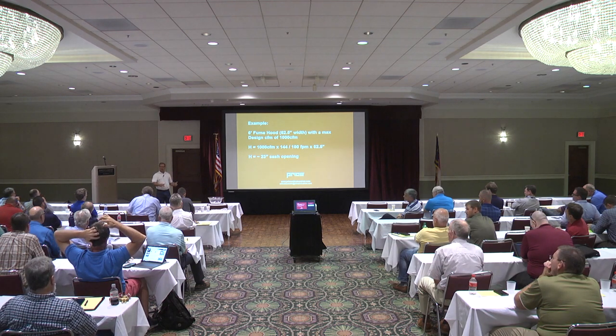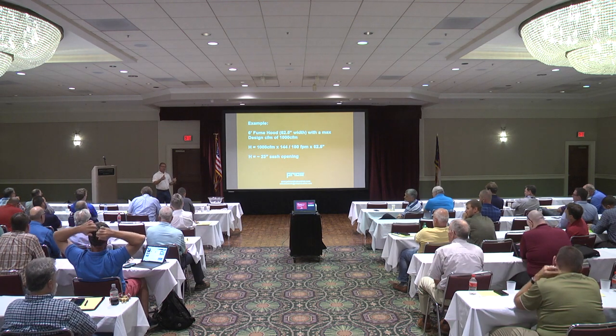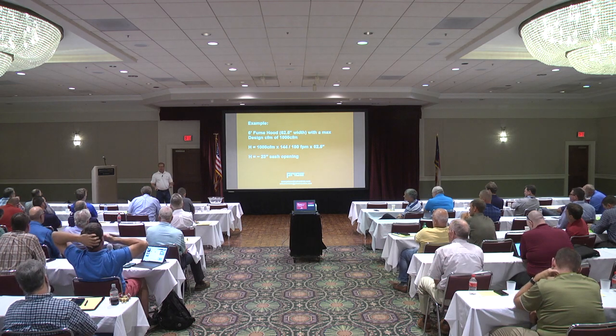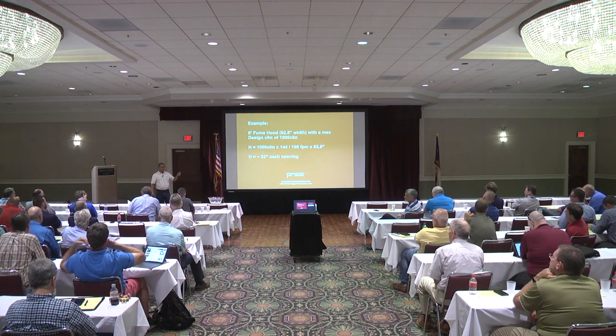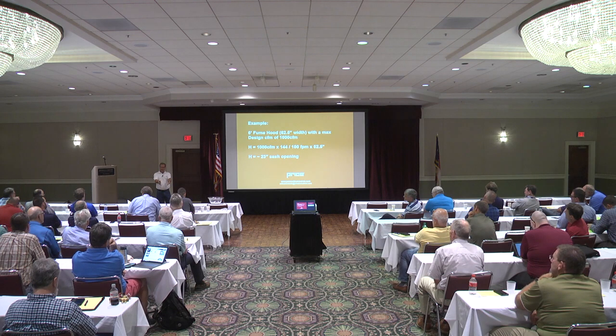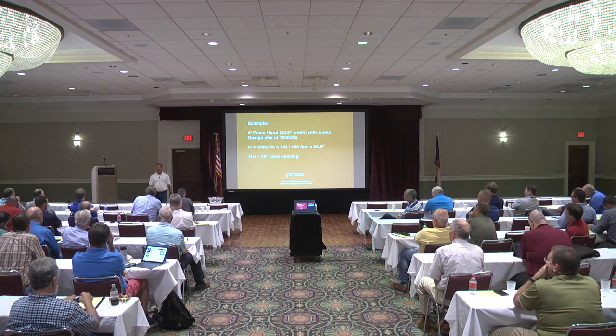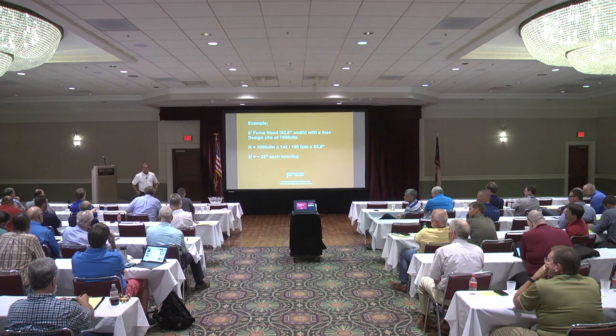The reverse is a problem too, because you'll send it back to me and say, Dean, you didn't meet the velocity. But I met the CFM. The document says 600. I gave you 600. We didn't design it properly. But from a safety standpoint, I'm only looking at contract documents that I've got to deliver the project to.